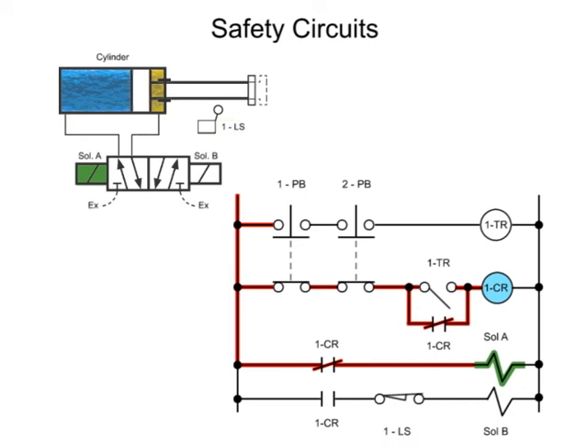At this point in the cycle, the cylinder will remain extended indefinitely until at least one push button is released. If one push button is released, the control relay will lose power, which causes 1-CR to remove power from solenoid A and connect power to solenoid B.